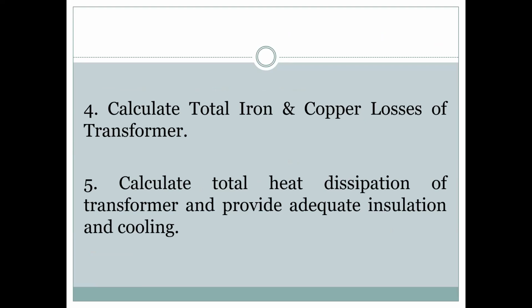Now this is the one. Calculate heat dissipation. Here the thermal engineering comes into the picture. How much heat is generated by the transformer without cooling? First, we have to find out the heat generated by the transformer itself. Then only can we give you the cooling system. This will be cooled. Oil quantity is to be decided. The number of radiator fins has to be decided. The number of radiators has to be decided. All of it comes from this calculation of heat dissipation.